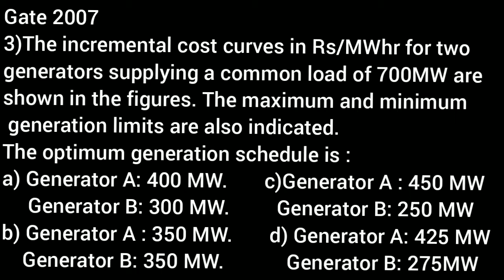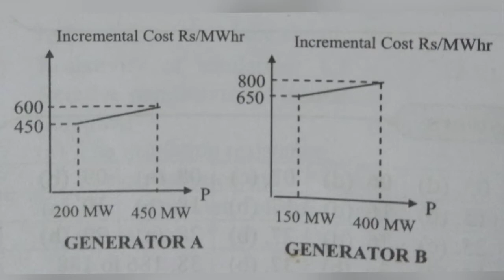That is the question that came in 2007. The incremental cost curves in rupees per megawatt hour for two generators supplying a common load of 700 megawatt are shown in the figures. The maximum and minimum generation limits are also indicated. The optimum generation schedule is: from the figure, it is given that the incremental fuel cost of generator A for maximum power generation is equal to 600 rupees per megawatt hour. The incremental fuel cost of generator B for minimum power generation is equal to 650 rupees per megawatt hour. As the incremental fuel cost of generator A is less as compared to that of generator B, we can operate generator A at its maximum output of 450 megawatt and the remaining will be generated by generator B. So, option C is the right answer. So, let's move to the next question.